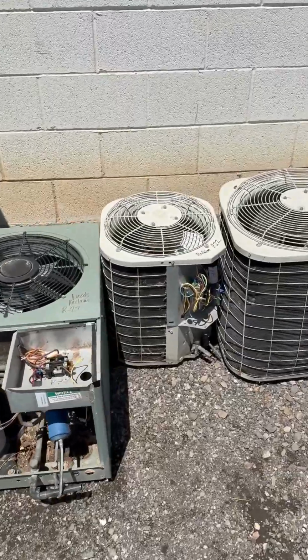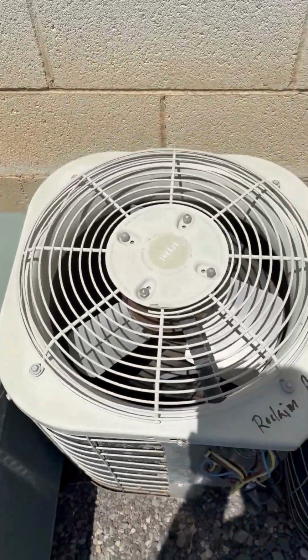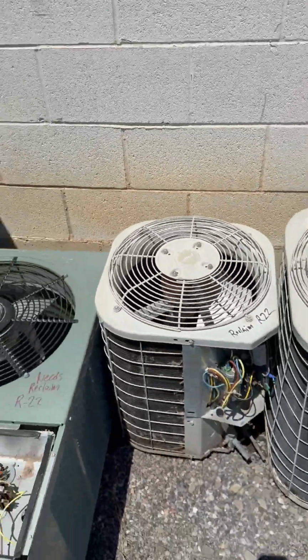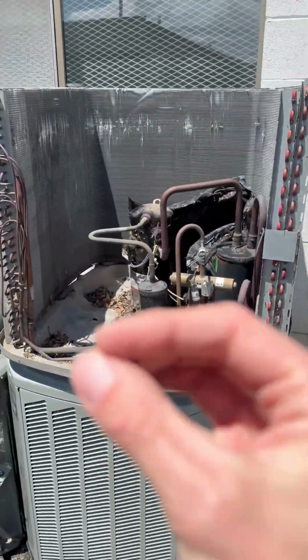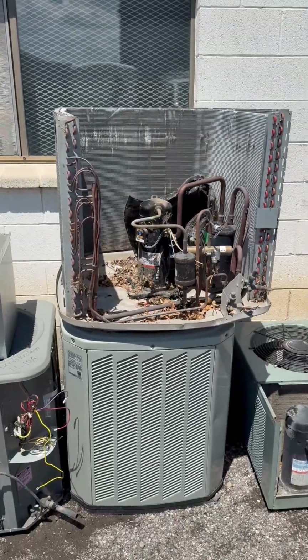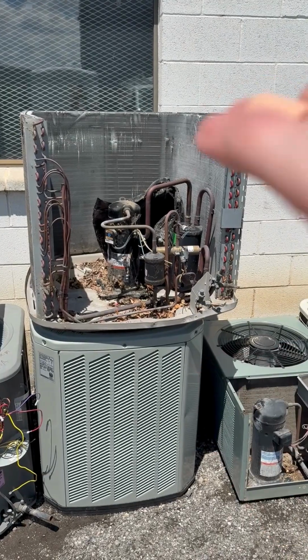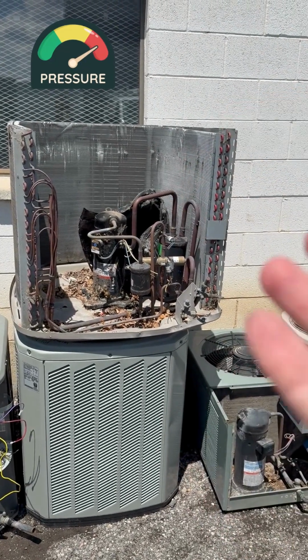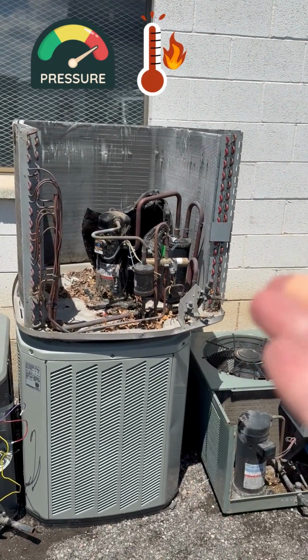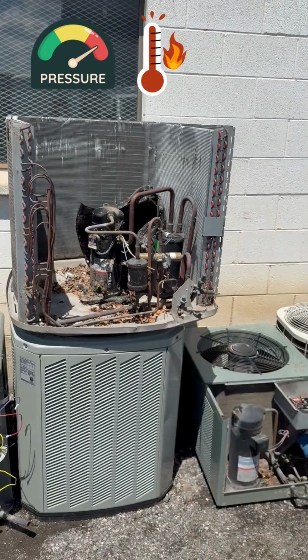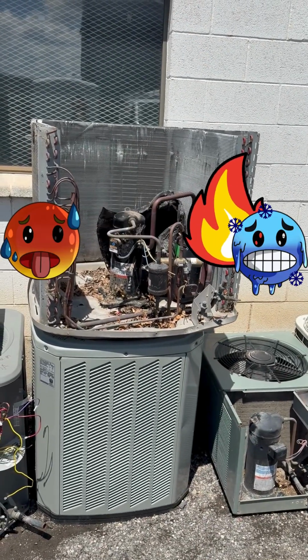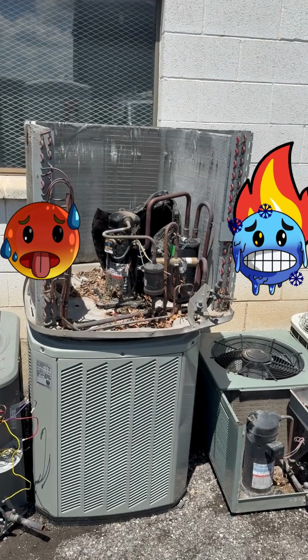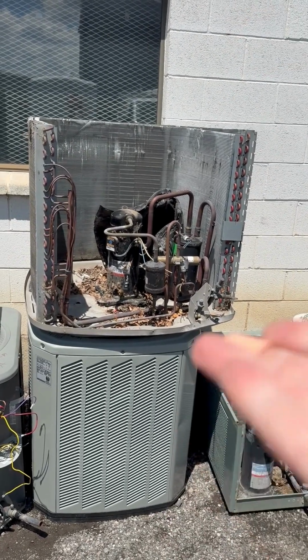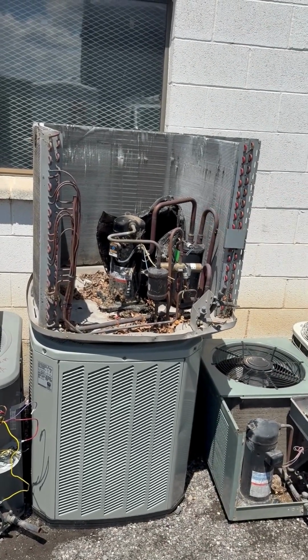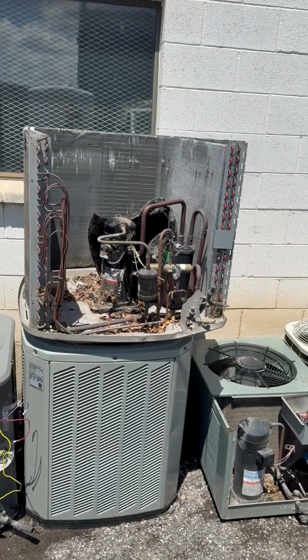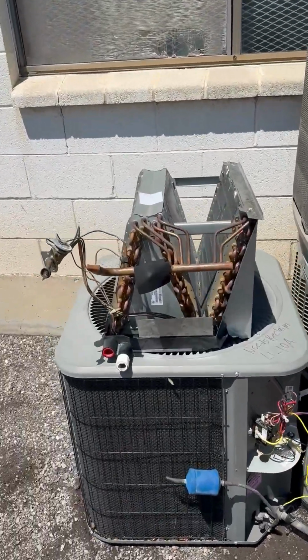That's why we have all of these fans on the top. It's going to absorb the heat from your home, and then I compress that heat that I absorbed through the evaporator coil into a higher pressure, and with higher pressure comes higher temperature. That higher temperature is generally higher than the outdoor temperature, and heat always goes to where there's less heat. So I'm elevating the pressure, which elevates the temperature of the indoor heat that we just absorbed, to want to go outside.